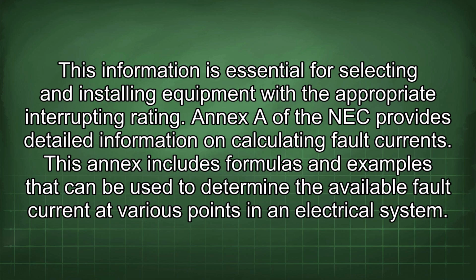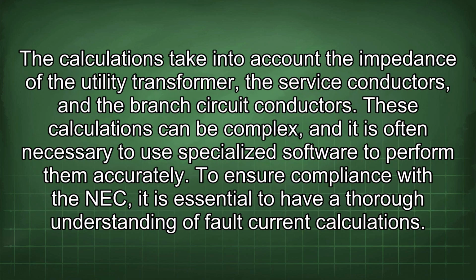Annex A of the NEC provides detailed information on calculating fault current. This annex includes formulas and examples that can be used to determine the available fault current at various points in an electrical system. The calculations take into account the impedance of the utility transformer, the service conductors, and the branch circuit conductors. These calculations can be complex, and it is often necessary to use specialized software to perform them accurately.